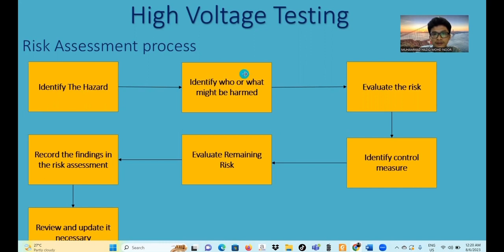And the second step, we need to identify who, a person or what thing, might be harmed during the high voltage testing. And the third is we need to evaluate the risk, whether the risk is high risk, moderate risk or low risk. And next, after we evaluate the type of risk that we need to face during the high voltage testing inside the laboratory, we need to identify the control measure in order to overcome the risk that we will face.